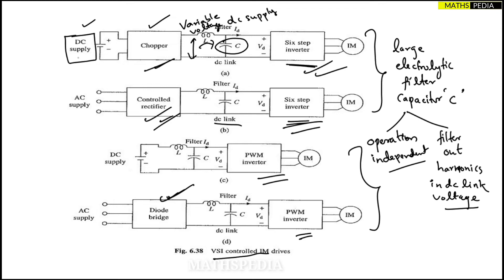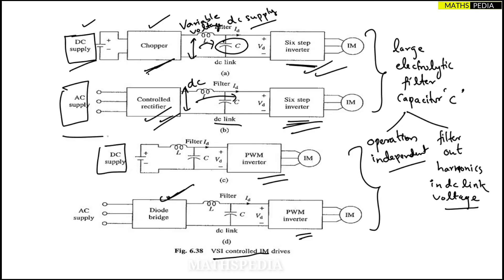Whenever a DC supply is present, a chopper is used to convert it to variable voltage DC supply for the inverter. When AC supply is present, a controlled rectifier is used to convert AC to DC as input for the six-step inverter. For the PWM inverter case, when DC supply is available it can be connected directly. When AC supply is present, a diode bridge rectifier is used to convert AC to DC for the PWM inverter.